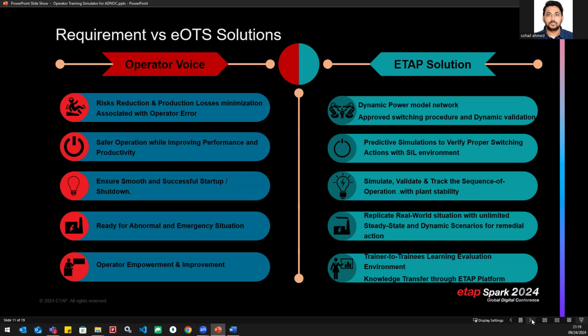Another key feature is the fact that the relay protection model within the ETAP is taken into account by the simulator. For instance, if an overcurrent relay is modeled, it will automatically trip the breaker if the required current is detected. Dynamic response combined with the relay protection reveals critical information that many operators may not have known previously.